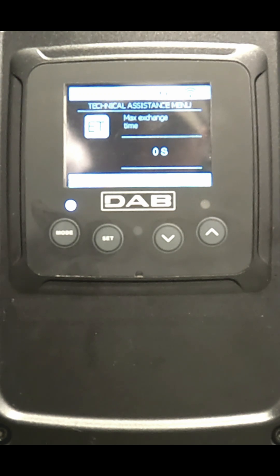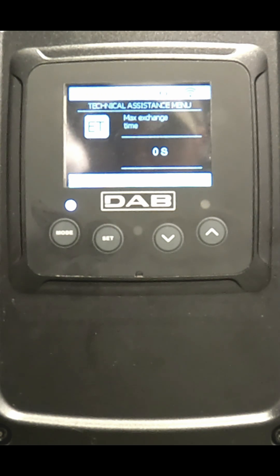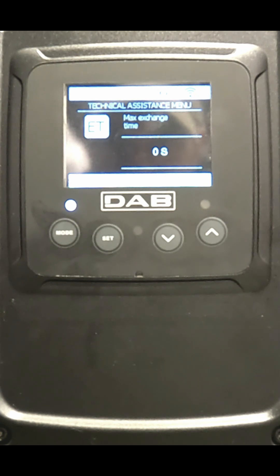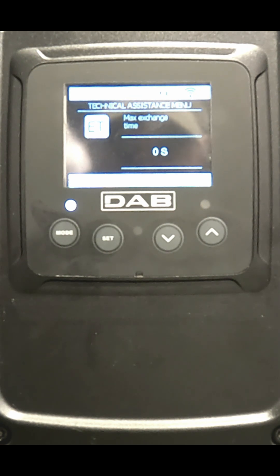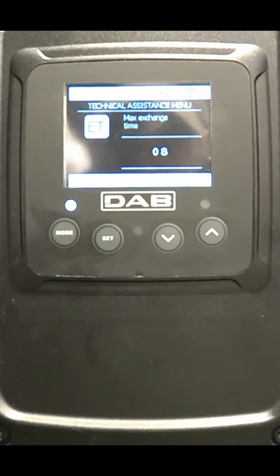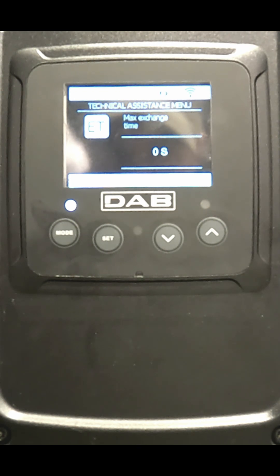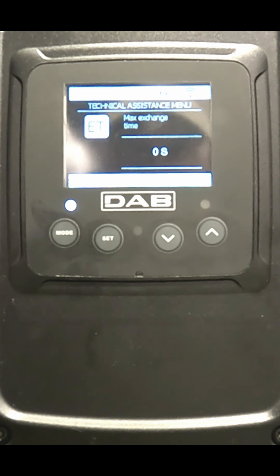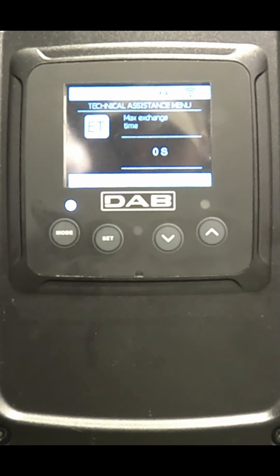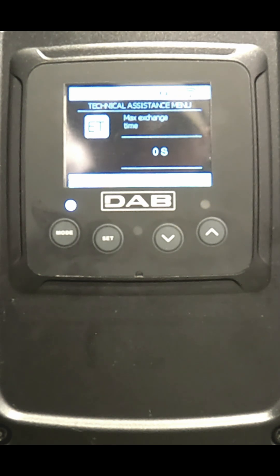This is somewhat different from some of the other Esybox line pumps because the max exchange time comes set at 0 seconds. What that means is that every time your pump set starts up, a different pump will start as the lead pump.